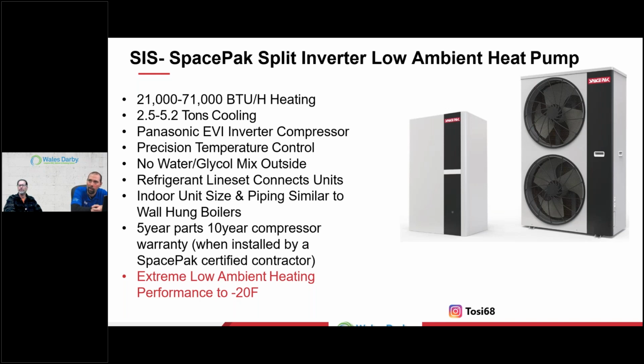It says no water glycol mix, but that's really, there's nothing outside. Right. We still wanna run at minimum of 10 to 15% glycol. Just because it's not so much, we're not worried about outdoor, obviously, but you do have a refrigerant to water heat exchanger inside that indoor unit where there is a possibility with the lower refrigerant temps, right, you could freeze the water in a heat exchanger. So that's what we're trying to avoid there. Yeah, you're approaching those thresholds of cold water potentially freezing the indoor unit's heat exchanger.